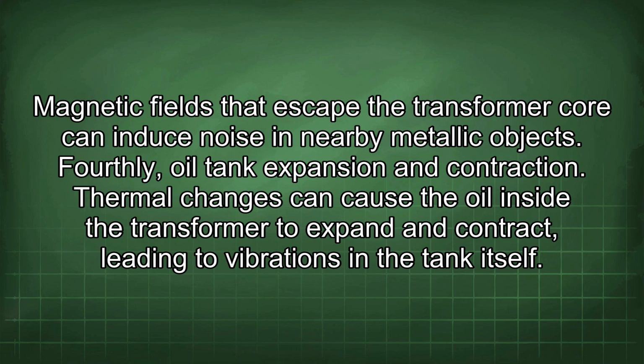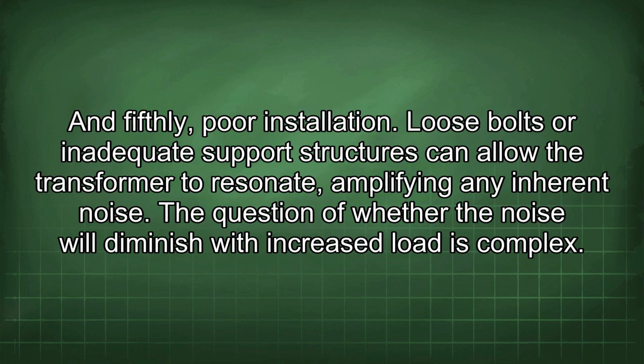Fourthly, oil tank expansion and contraction. Thermal changes can cause the oil inside the transformer to expand and contract, leading to vibrations in the tank itself. And fifthly, poor installation. Loose bolts or inadequate support structures can allow the transformer to resonate, amplifying any inherent noise.